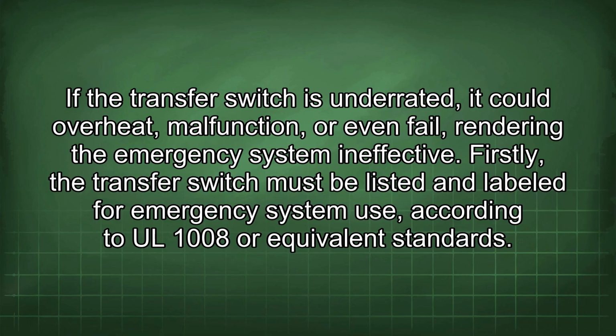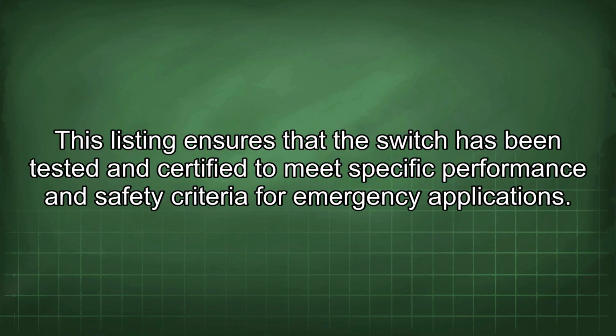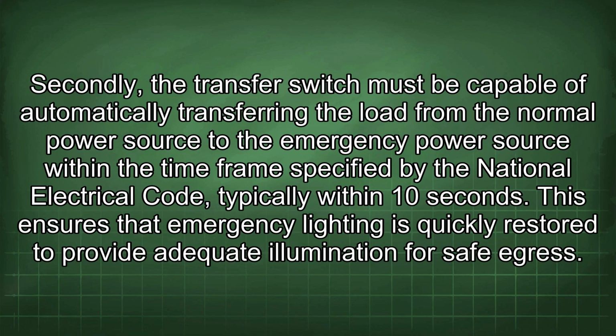Firstly, the transfer switch must be listed and labeled for emergency system use, according to UL 1008 or equivalent standards. This listing ensures that the switch has been tested and certified to meet specific performance and safety criteria for emergency applications. Secondly, the transfer switch must be capable of automatically transferring the load from the normal power source to the emergency power source within the time frame specified by the National Electrical Code, typically within 10 seconds. This ensures that emergency lighting is quickly restored to provide adequate illumination for safe egress.